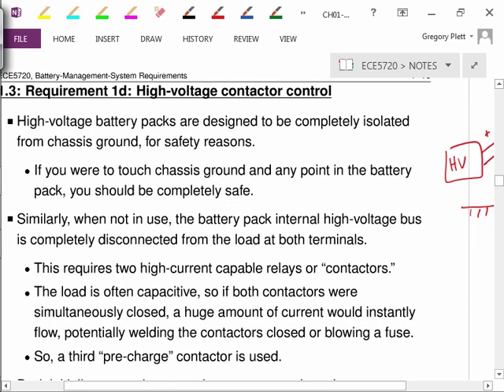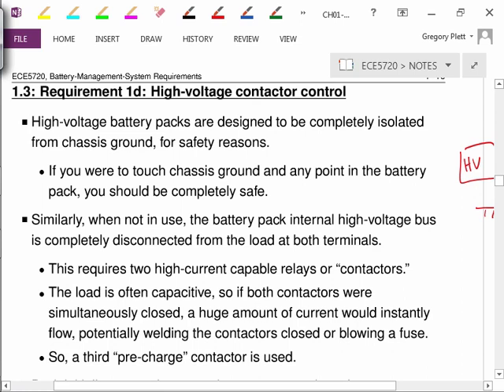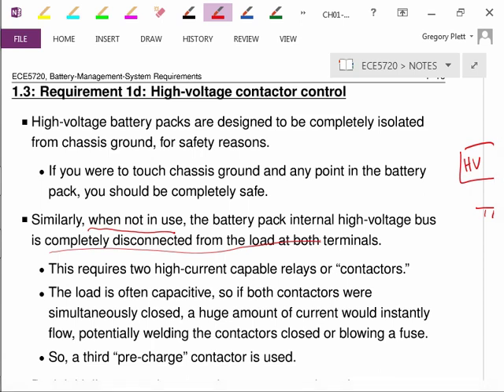In this section, we're going to focus more on another issue related to the high voltage, high current nature of a battery system, and that's how do you connect the battery to the load. It sounds like a simple thing, but it takes some consideration to do it properly. When the battery system is not in use, the high voltage bus is completely disconnected from the load at both terminals. Again, we want to minimize the possibility of someone mistakenly touching both terminals somehow and electrocuting themselves. One way of minimizing that possibility is to simply disconnect the battery pack from the external terminals of the battery pack when it's not in use.